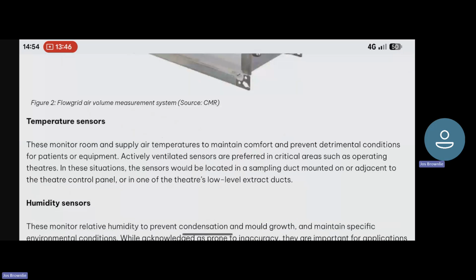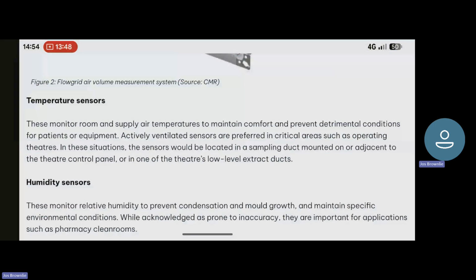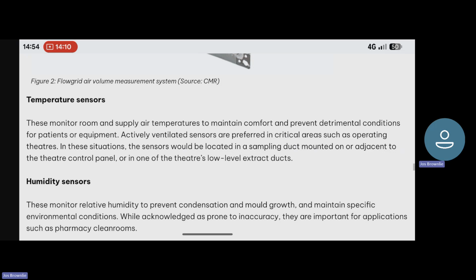Temperature sensors. These monitor room and supply air temperatures to maintain comfort and prevent detrimental conditions for patients or equipment. Actively ventilated sensors are preferred in critical areas such as operating theatres. In these situations, the sensors would be located in a sampling duct mounted on or adjacent to the theatre control panel, or in one of the theatre's low-level extract ducts.